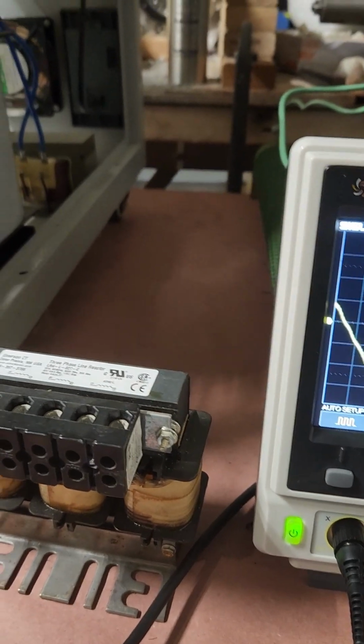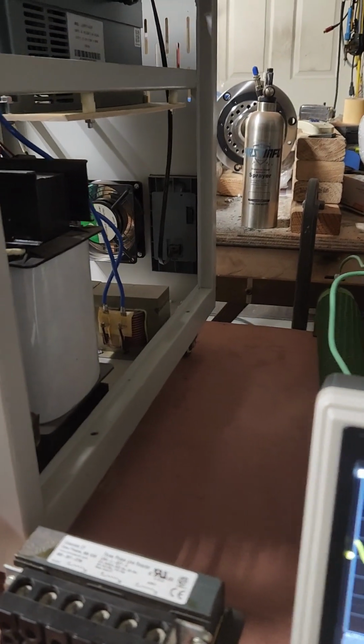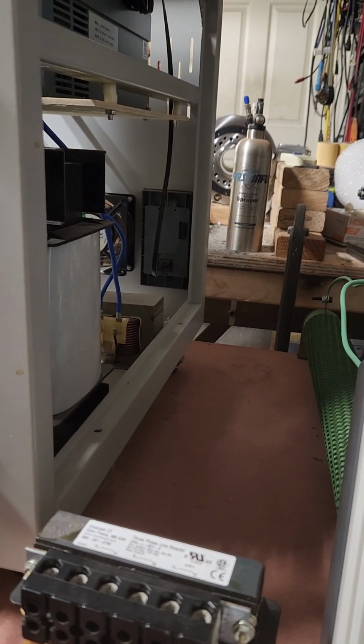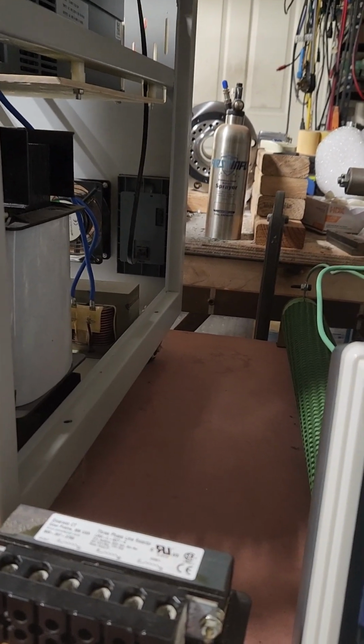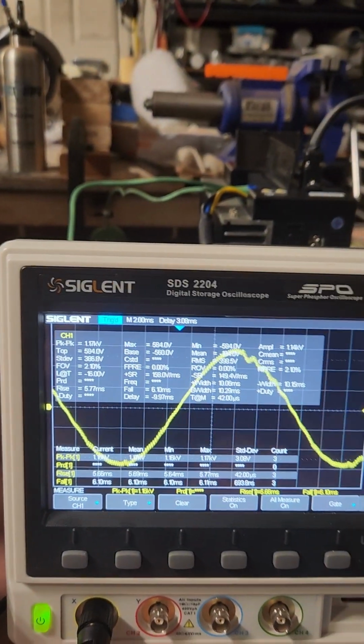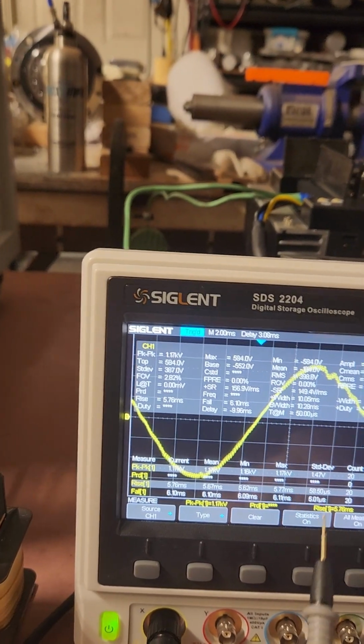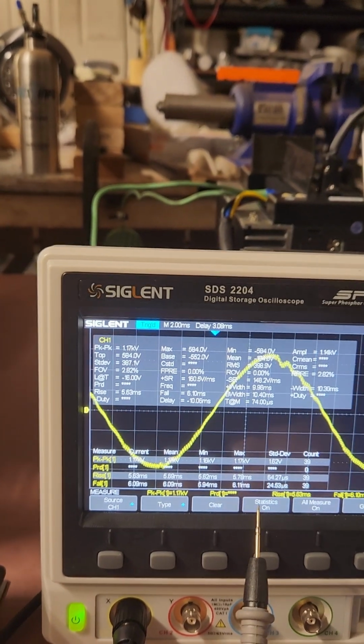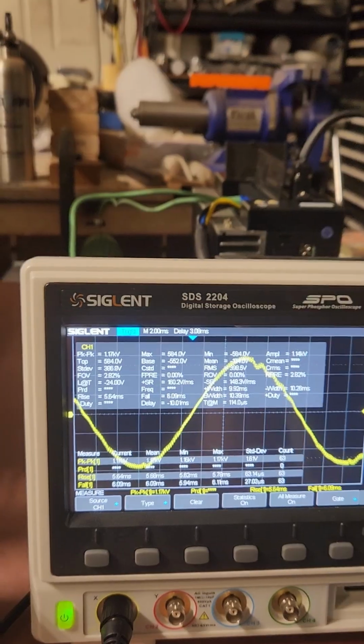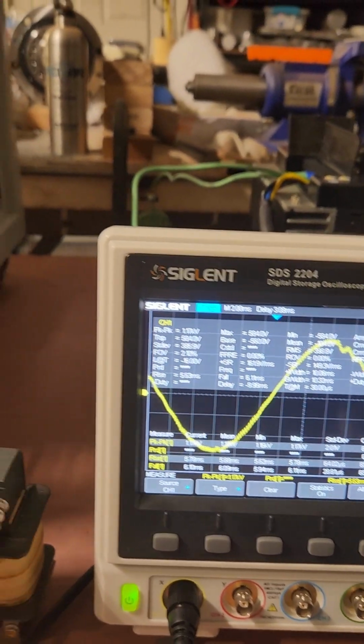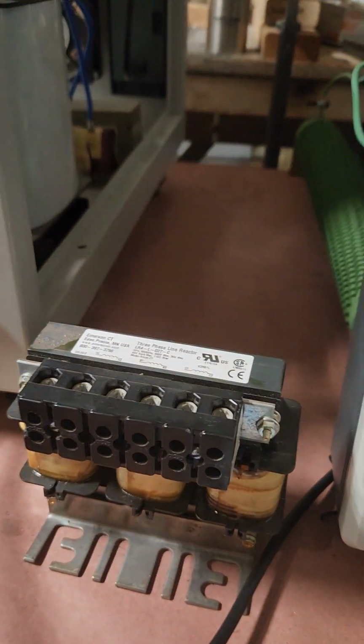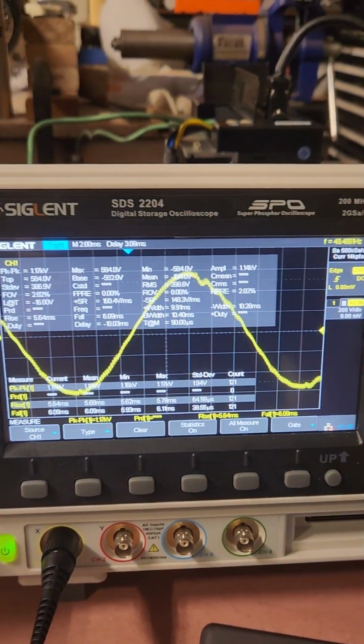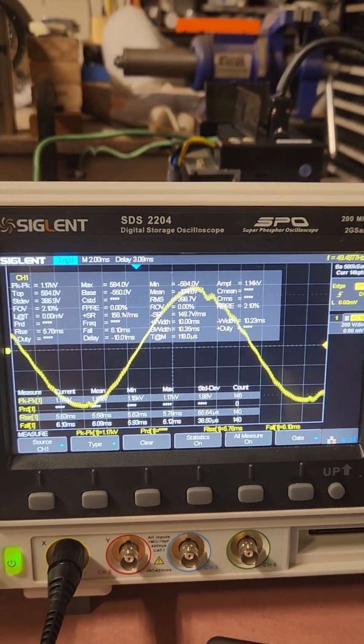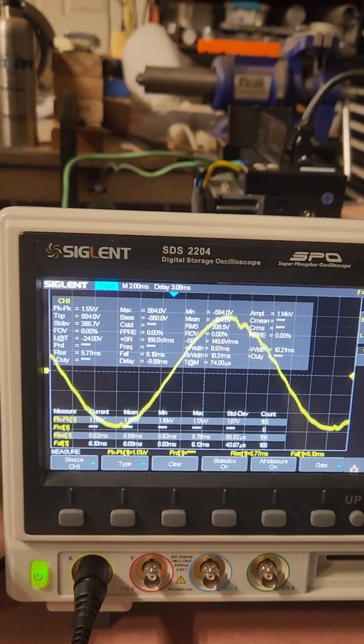So these two actions I'm going to take: change the VF frequency in the drive so that at 50 hertz I get about 370 volts — since 370 plus those 40 volts gives me 410, maybe I'll go even lower — and then add this reactor to try to eliminate that chopping, and then try to power the motor.